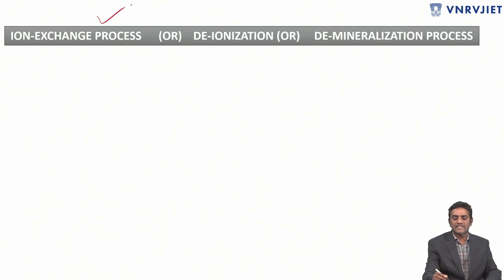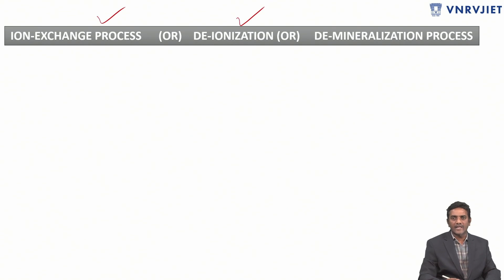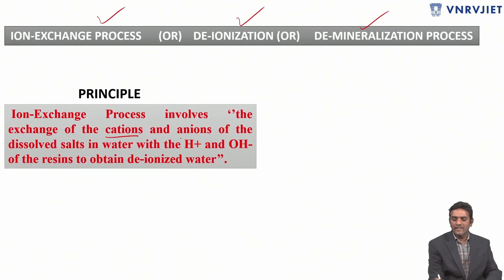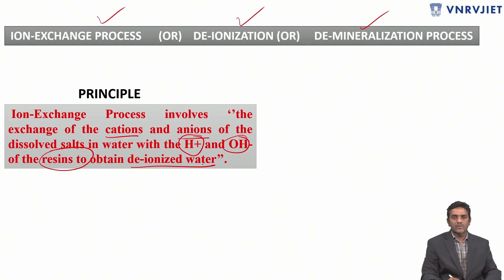The ion exchange process is also called deionization, because all unwanted ions are replaced from water except H⁺ ions and OH⁻ ions. It is also called demineralization. Here we are replacing the unwanted cations and anions with H⁺ and OH⁻ ions attached to resins, in order to obtain deionized water — that is the principle.